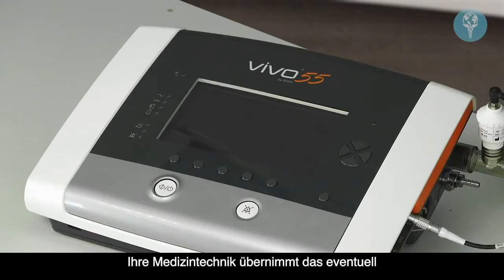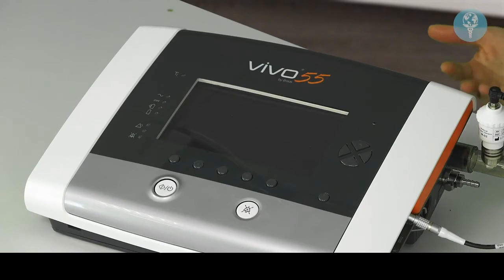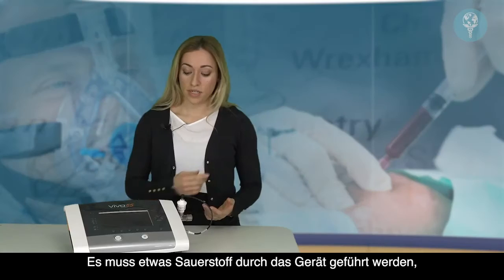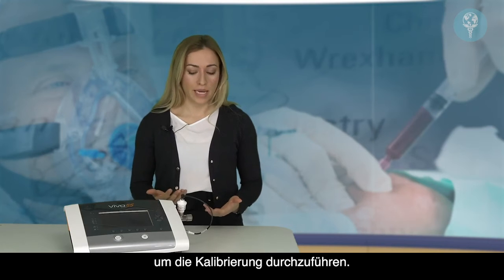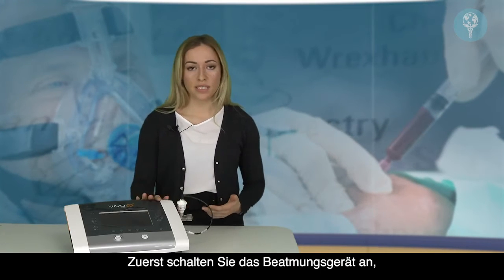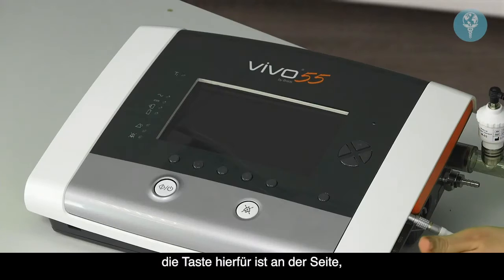Once you've got the FiO2 sensor set up and connected, you'll first need to calibrate the sensor. Your medical physics department may do this for you already. You will need some oxygen entrained through the device in order to be able to perform the calibration. First you'll need to switch on the ventilator. We'll just push that on, one push of the button on the side.